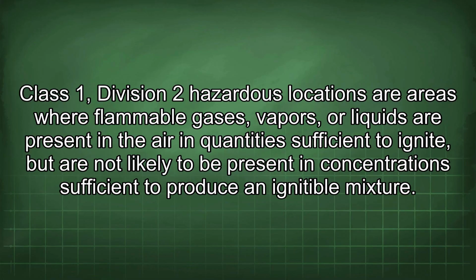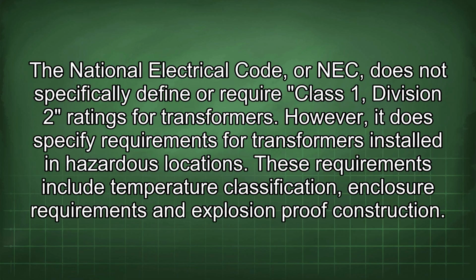Class 1, Division 2 hazardous locations are areas where flammable gases, vapors, or liquids are present in the air in quantities sufficient to ignite, but are not likely to be present in concentrations sufficient to produce an ignitable mixture. The National Electrical Code, or NEC, does not specifically define or require Class 1, Division 2 ratings for transformers. However, it does specify requirements for transformers installed at hazardous locations.